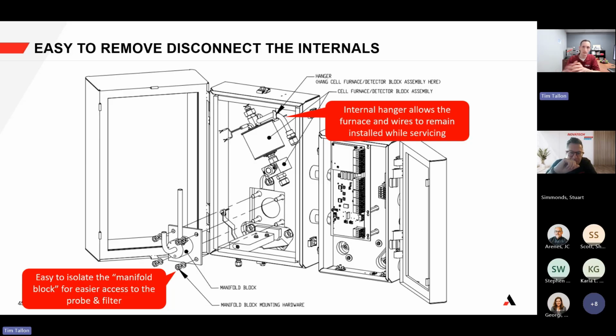So it's easy to remove and disconnect from the internals—you can have it wired up to the electronics board and put it on a little hanger. It's a small thing, but it helps a lot for accessing it. By disconnecting right here, you can then remove the manifold block, using the 4-bolt pattern to make it easier to isolate and remove. This is installing it, but it's the same idea for removing the probe and filter.